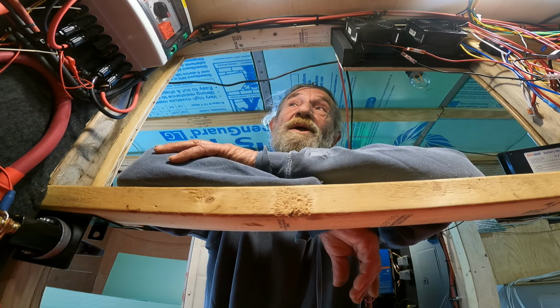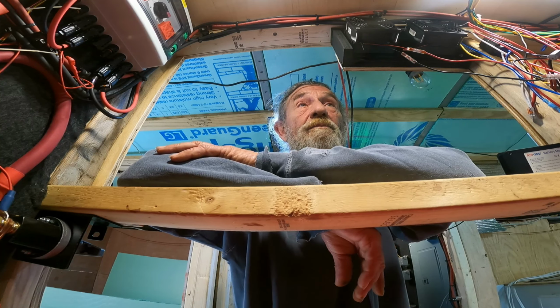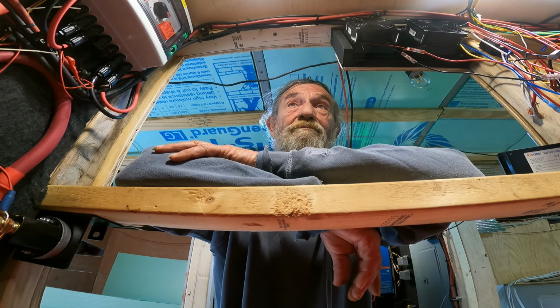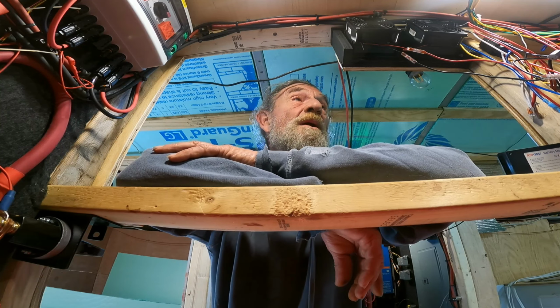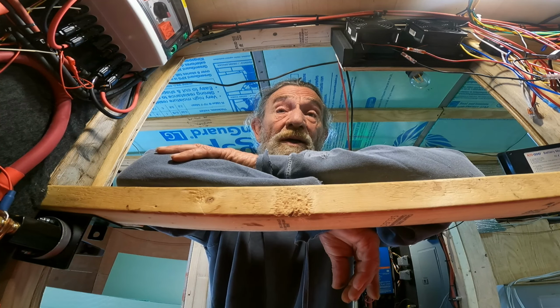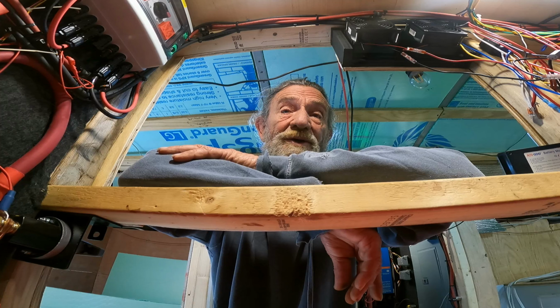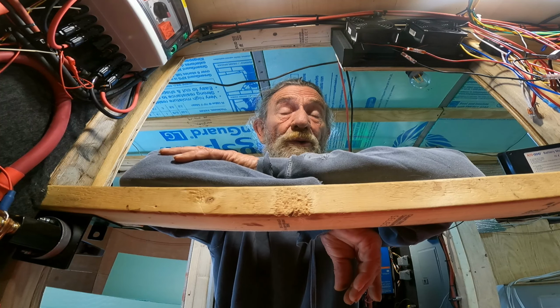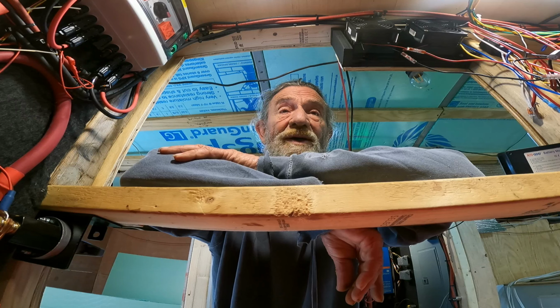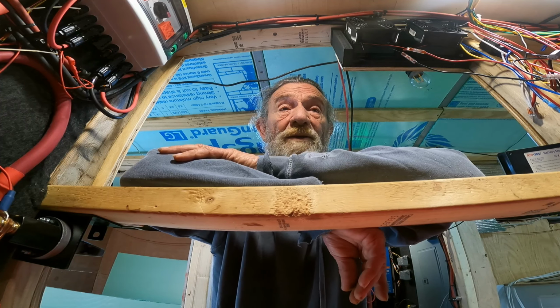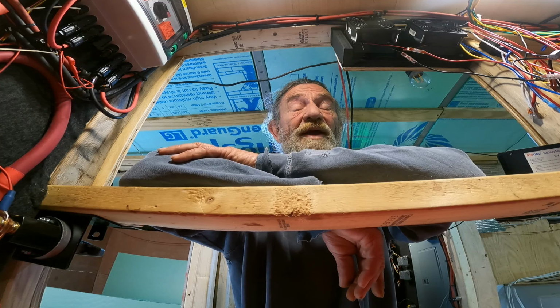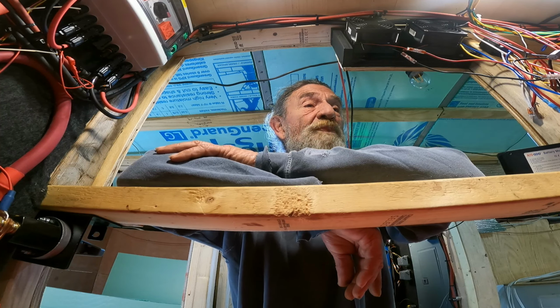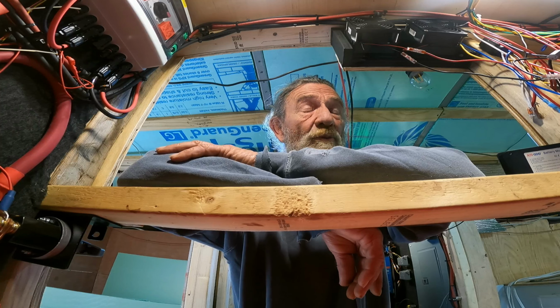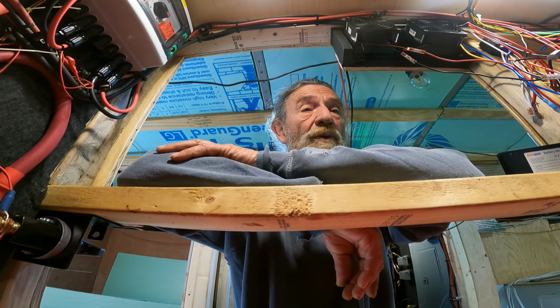Maybe it's better, I don't know, but a standard $5 cable replaced a Victron cable that cost probably twice as much, if not more. So as a test, I've got Victron cables running my VE bus connections, but I don't like them because they're too short. I have longer Cat 5 cables, and I'm going to try using those for the VE bus connections to see if they work as well. If there are any issues, I'll let you know. The daisy chain cable between the inverters I'll leave as Victron since it's short enough, works well, and would be a pain to remove. But all the other cables I'm going to try to change and see how that works.